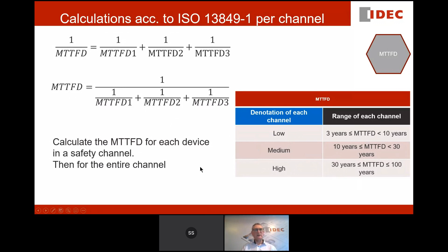There's one independent, free-access tool called SISTEMA. And SISTEMA is a tool where everybody can enter their data on their B10D, and then they can enter in their MTTFD if it's appropriate. And that allows the customer to then make his own calculations on how to check his performance levels on his machine. Most important thing, MTTFD is defined by low, medium, or high, and the range of low is 3 to 10 years, medium is 10 to 30 years, and high is 30 to 100 years. And we do that for the entire channel.